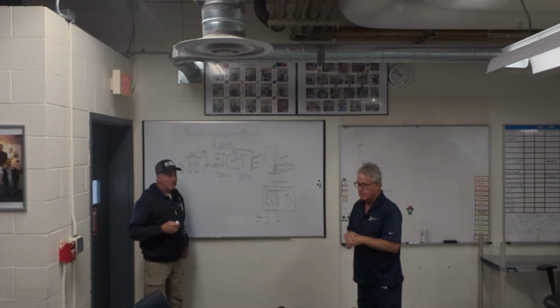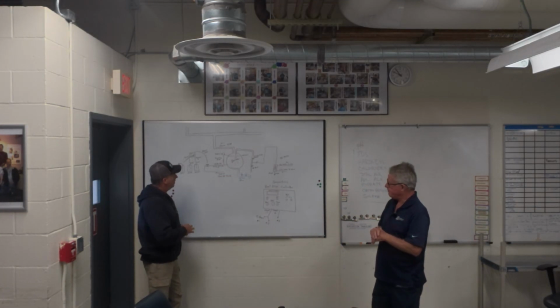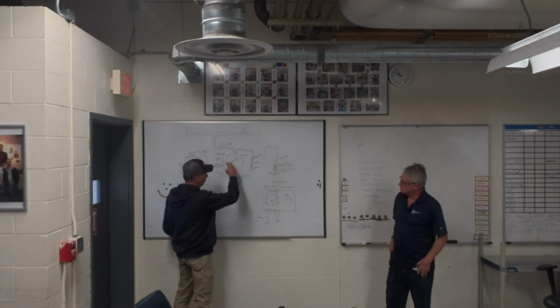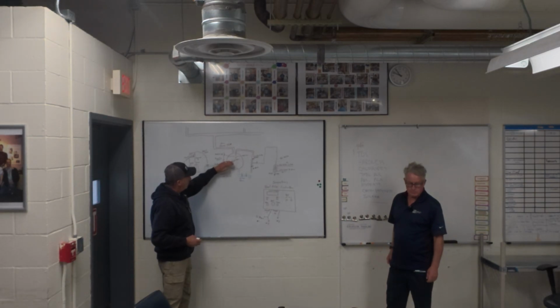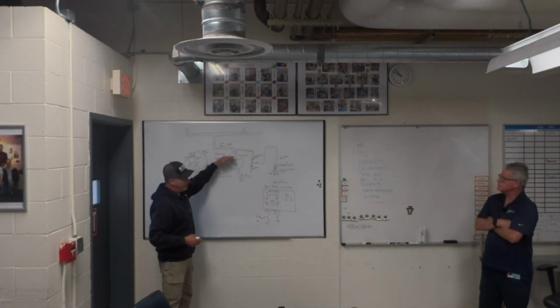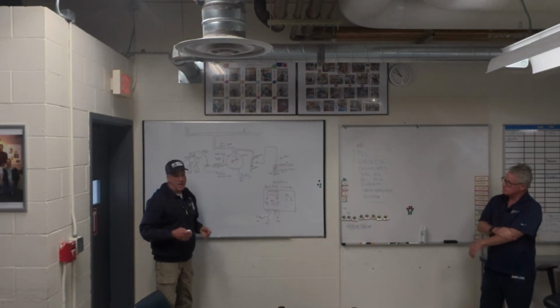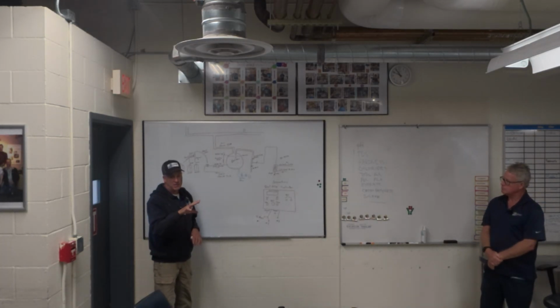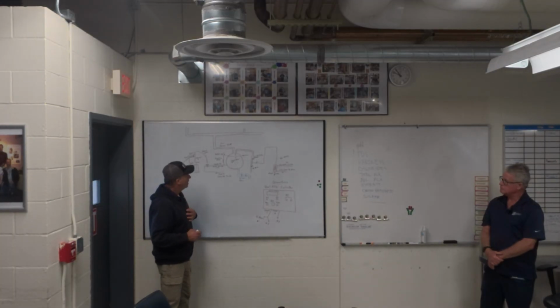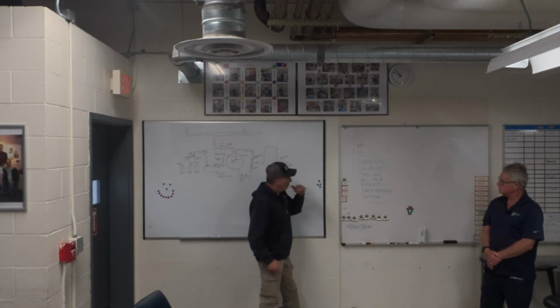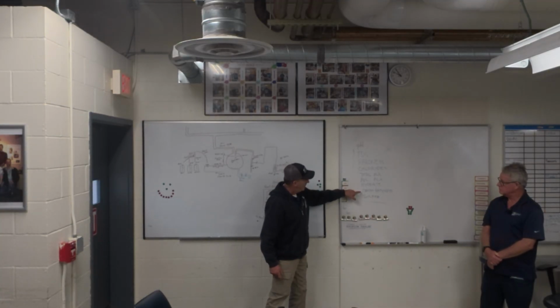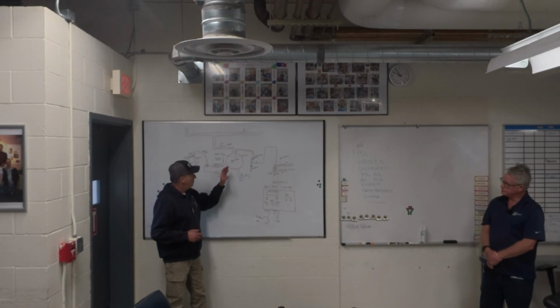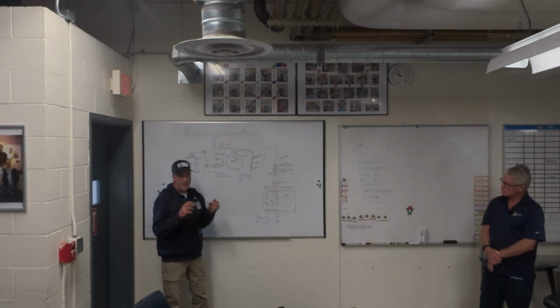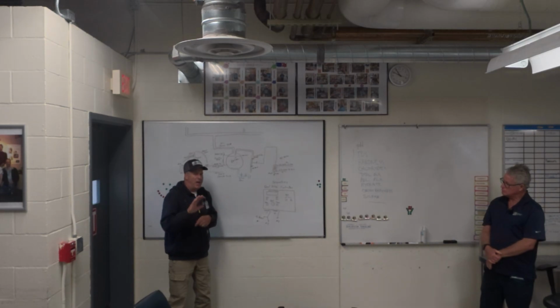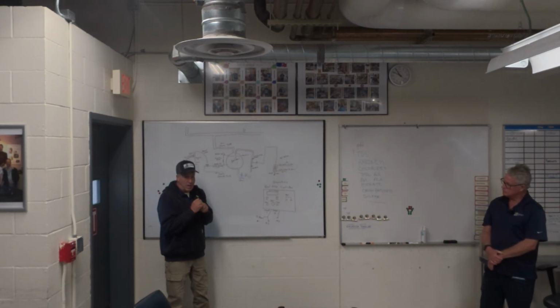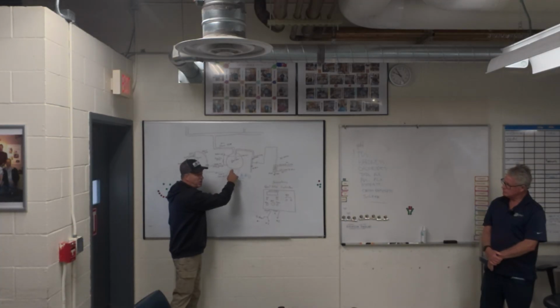Thank you. So just to help elucidate that question, the minerals that are in solution in the boiler are happily in solution. When the water evaporates and becomes steam, what it leaves behind is concentrated. Left unchecked, that would start to plate out on hot surfaces and cause scale. So the chemicals we introduce, particularly when we have enough hydrate alkalinity present, in combination with the phosphate, cause the calcium to precipitate out. It's like, I'm not going to plate out on a hot surface, I'm just going to glom onto the acrylamides in there and form a harmless sludge at the bottom. Those are the reactants.